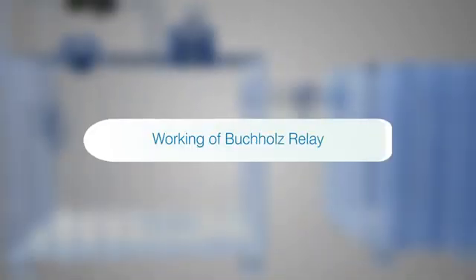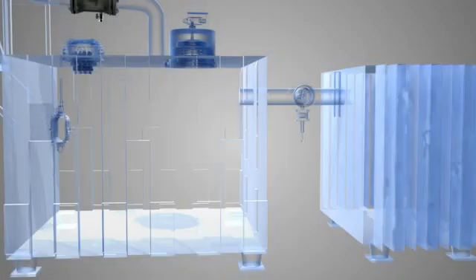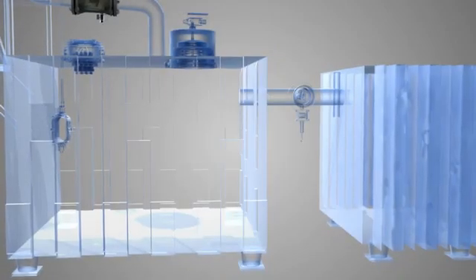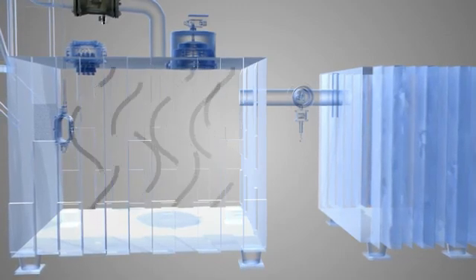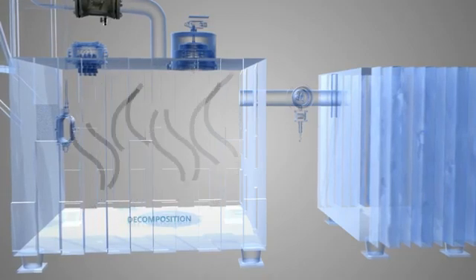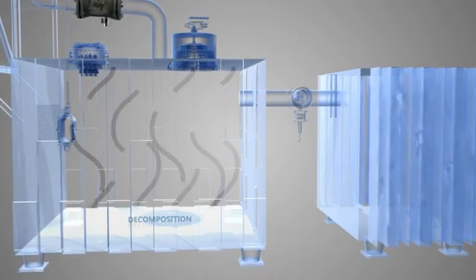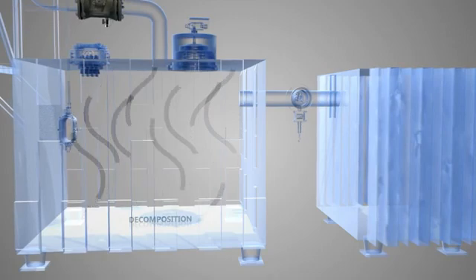Working of the Buchholz relay. Gas generation: Due to incipient faults, local heating takes place inside the transformer and as a result, a gradual decomposition of oil and solid insulating materials occur.